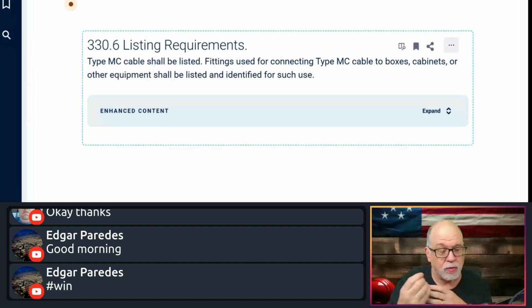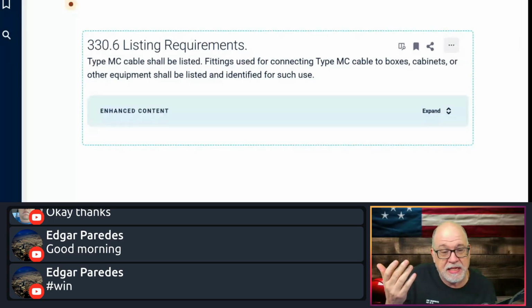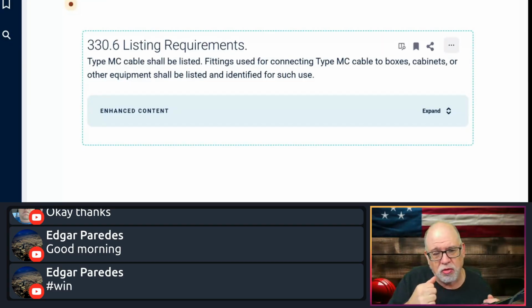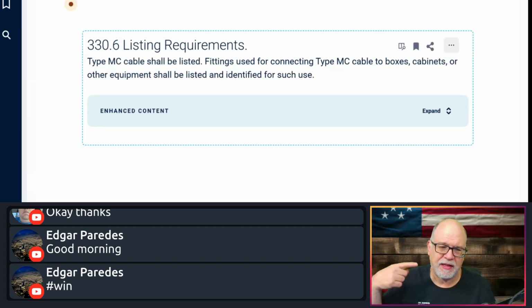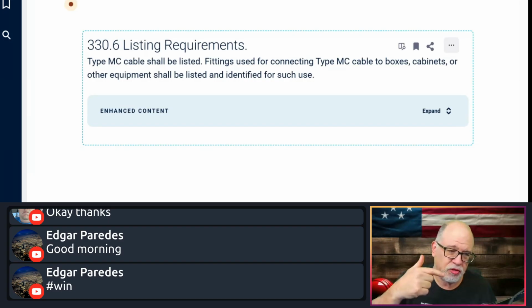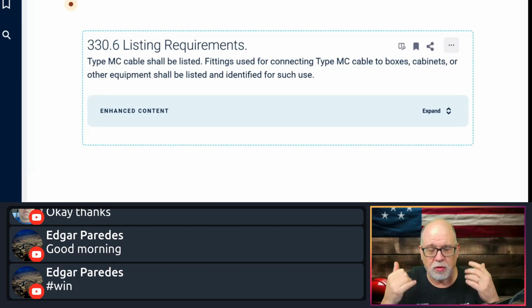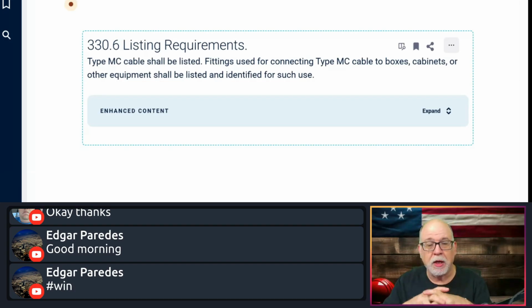But you have the smooth, which, for lack of a better explanation, kind of looks like EMT. It'll kind of look like an MI, whatever. It's just a continuous tube in that type of scenario. So that is a smooth MC. And then, of course, they make a corrugated or welded MC, which is basically like an interlock, but each convolution is welded together. Okay, so it is called continuous weld, or a corrugated type of MC. So that's your main types of MC: interlocked, smooth, and corrugated, or continuous weld.